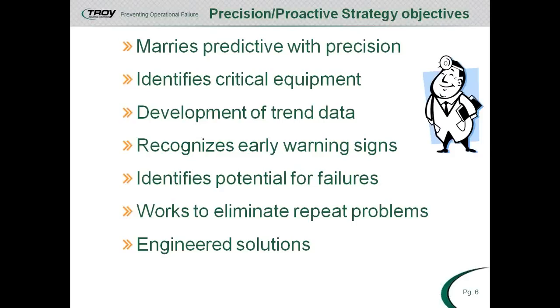Sounds, the way we go out and we do rounds, we look at things. Some companies are using ultrasound listening devices. They're placing their hands on the equipment and helping to recognize early warning signs. But we want to really stress that we need to start looking at using advanced instrumentation techniques to get early warning. Now, how about identifying the potential of failures or hazardous conditions? We'll know this ahead of time if we get current increases, or we're reading vibration data or thermal imaging data or ultrasonic data that tells us that something's changed.